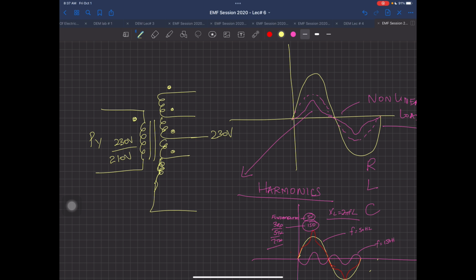Now for that 210 volts, you shift it and connect your load at this point. Now this time you're getting 230 volt. Otherwise if you connected it here, it was still giving you 210 volts. So these are taps here, and these taps are controlled by relays there, which are actually switching, first measuring the voltage coming from the supply, and then switching it accordingly.